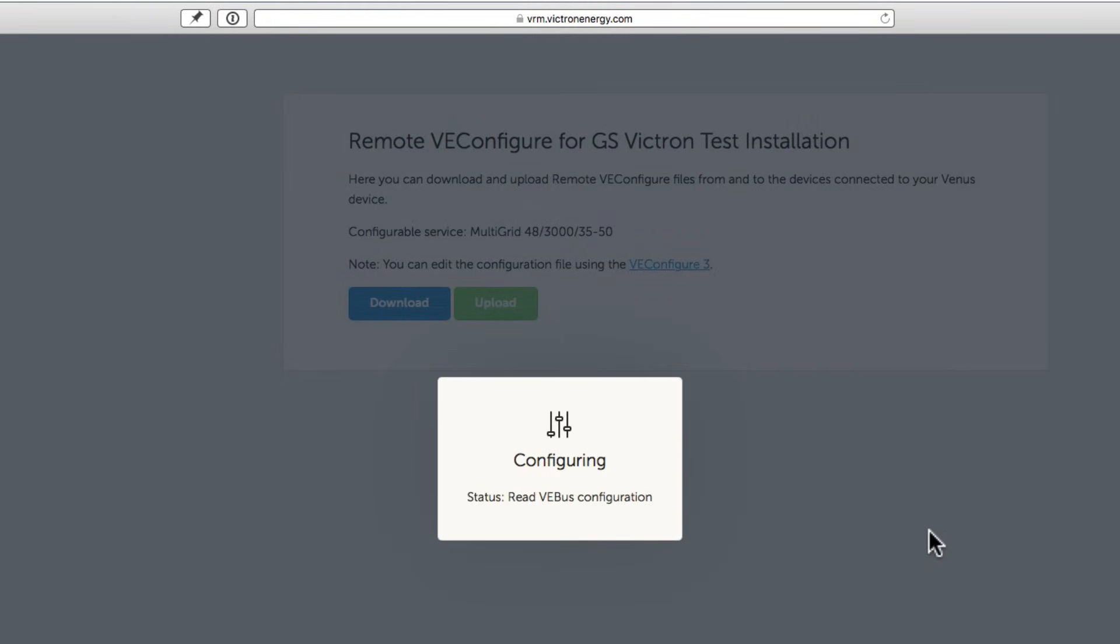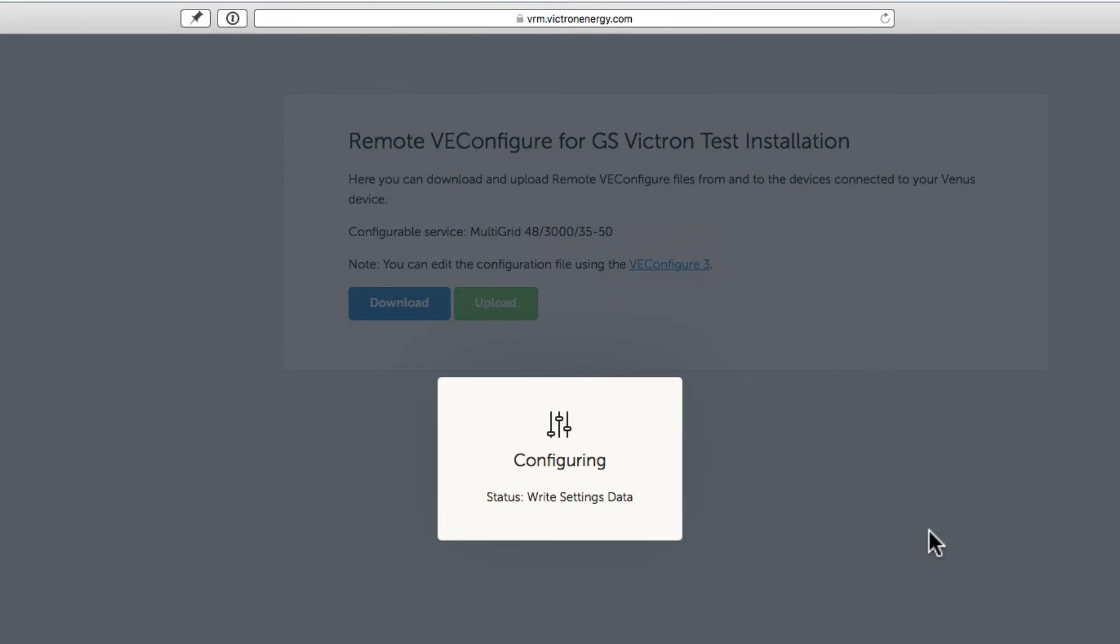In this case, the multigrid doesn't need to be restarted because the settings I changed aren't significant. If you were changing significant settings though, the multi-plus or the multigrid may restart itself and you may lose power if that's how the site is supplied. So be careful. You will receive a warning about this.